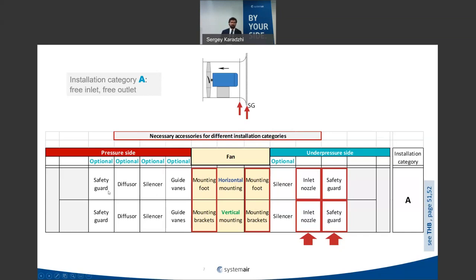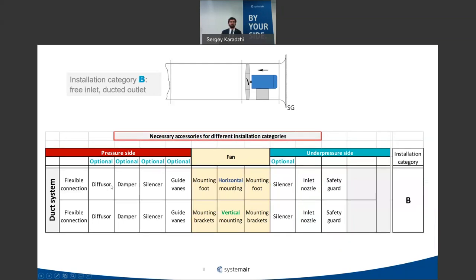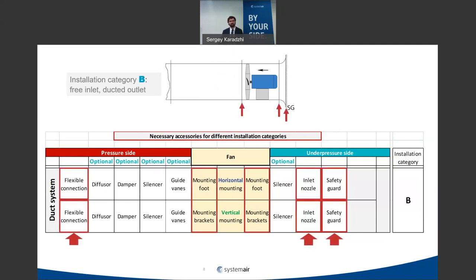For Category B — free inlet, ducted outlet — you also need an inlet nozzle and safety guard to smooth the inlet flow, mounting feet with dampers, and a flexible connection on the outlet. Without the flexible connection, vibrations can spread into the duct system, causing increased mechanical noise.